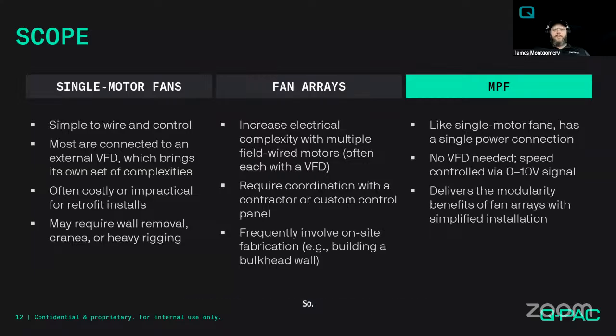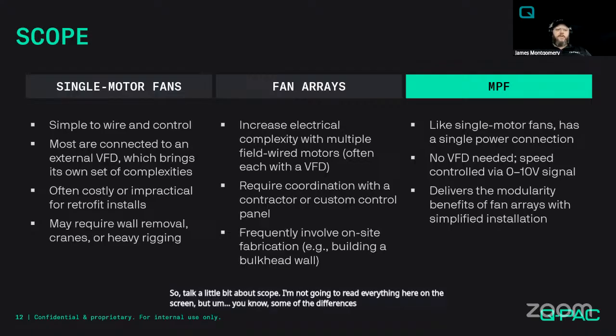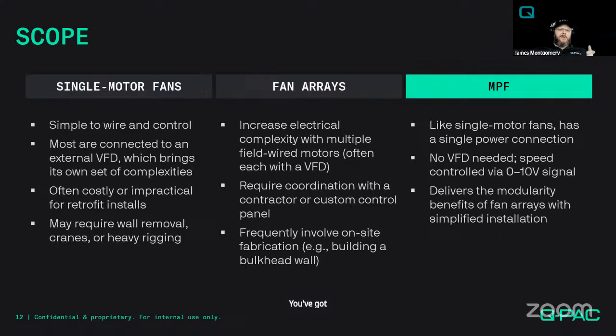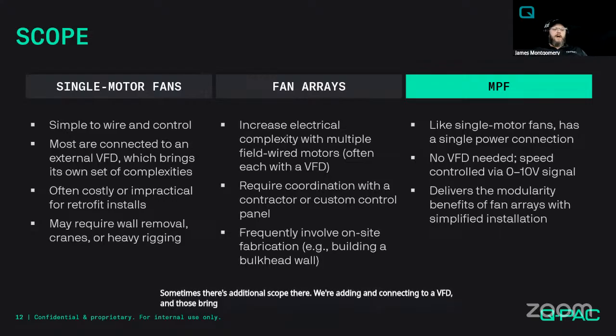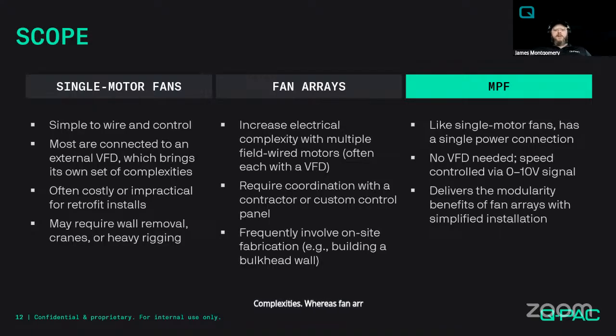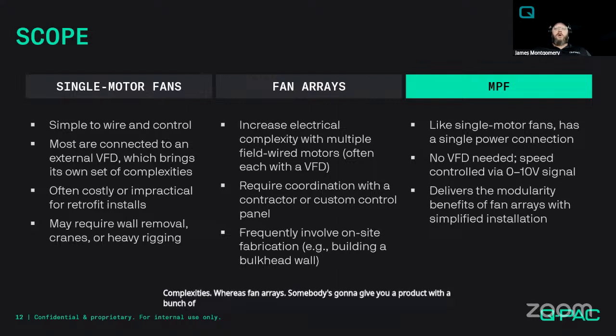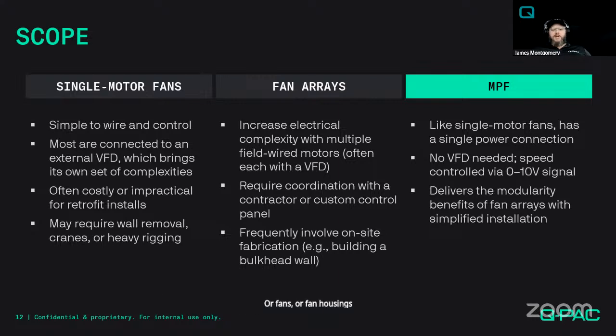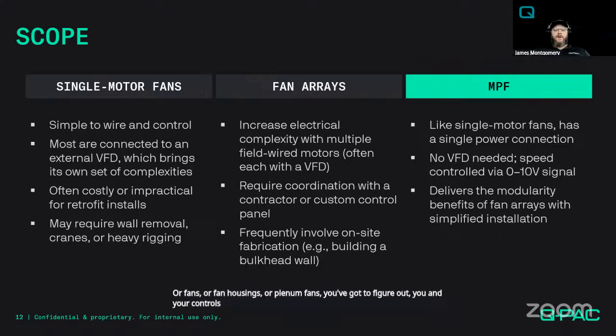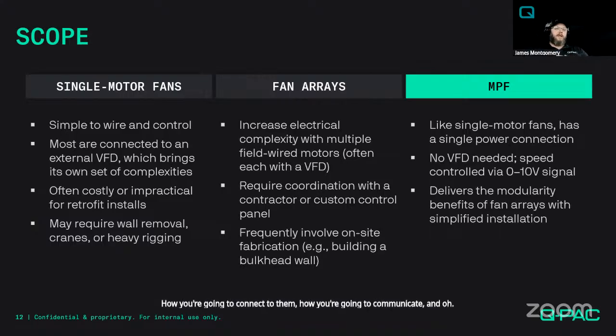So let me talk a little bit about scope. I'm not going to read everything here on the screen, but some of the differences. With the single motor fan, a lot of times you've got one simple AC motor that you're connecting to. But sometimes there's an additional scope there. We're adding and connecting to a VFD, and those bring on their own complexities. Whereas with fan arrays, somebody's going to give you a product with a bunch of cubes or fans or fan housings or plenum fans that you've got to figure out. You and your controls and your electrical contractor have got to figure out how you're going to interface with all of those things, how you're going to connect to them, how you can communicate. And oh, by the way, can we interface with our current BAS system if we have one? And so that frequently involves on-site fabrication and building.